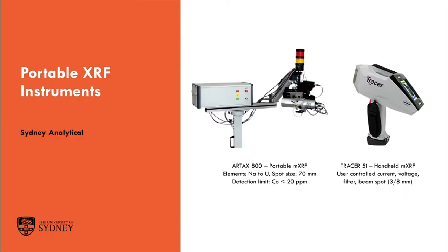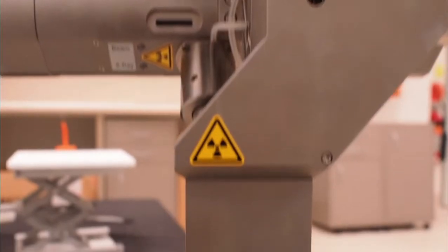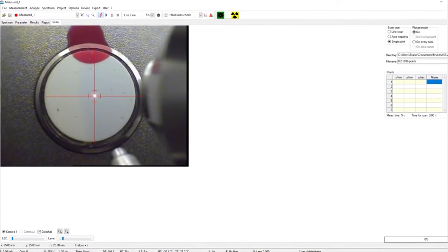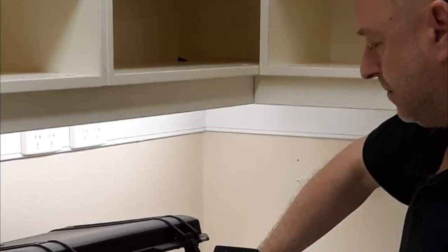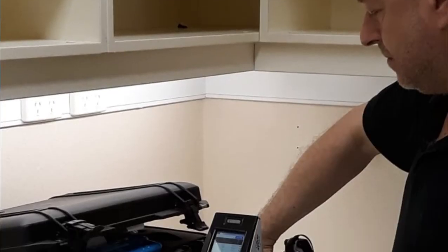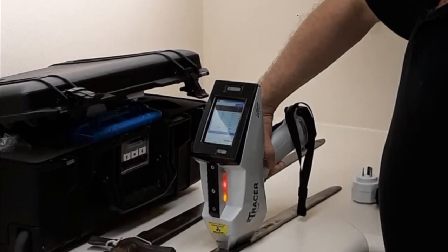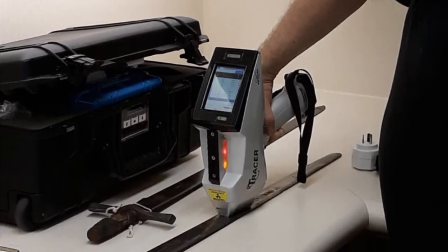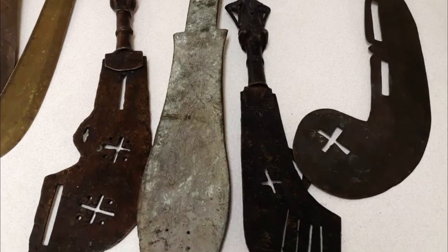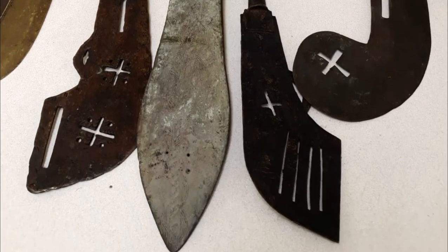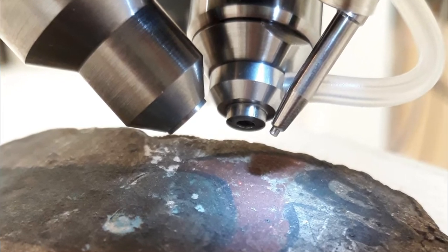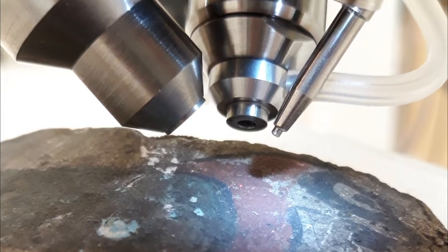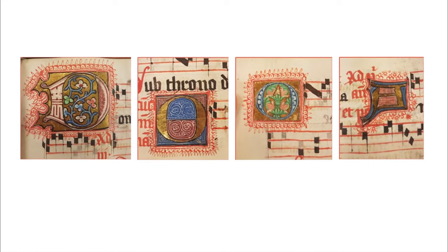At Sydney Analytical there are two main portable XRF instruments used in the analysis of cultural heritage materials. Used for the analysis of elements from sodium to uranium and covering spot sizes ranging from 70 microns to 8mm. These instruments are fast, cost effective, require little or no sample preparation and permit in-situ analyses particularly useful for large, cumbersome artefacts that may not otherwise fit into a sample chamber, such as large paintings. 2D mapping capabilities are used to generate element distribution maps from samples over an area of approximately 4.5 by 4.5 cm. This facilitates the investigation of small works on different supports and regions of interest within larger works. The micrometer spatial resolution further enables the investigation of layers.